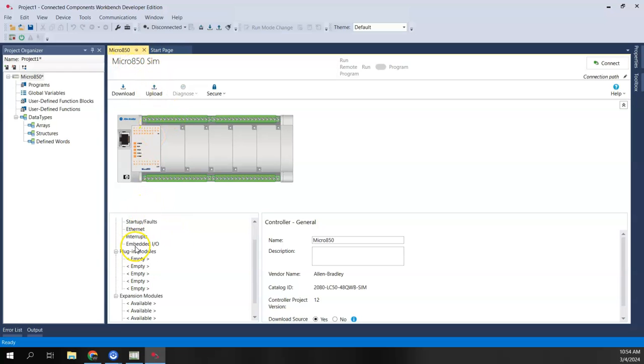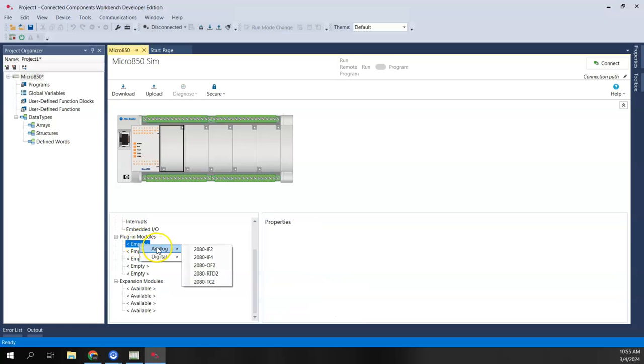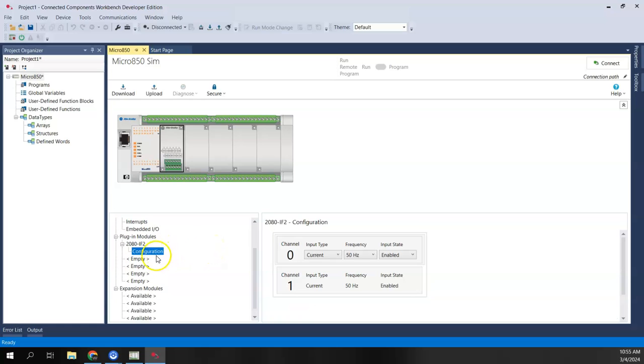Once we come into the Micro 850 tab, we have options to add plug-in modules. We don't need to configure an IP address or tie it to 127.0.0.1 here. What we do need to do is add the same plug-in modules we added to the simulator, because the simulator and the controller project have to match. I'll right-click and add an analog IF2 in the first plug-in slot.